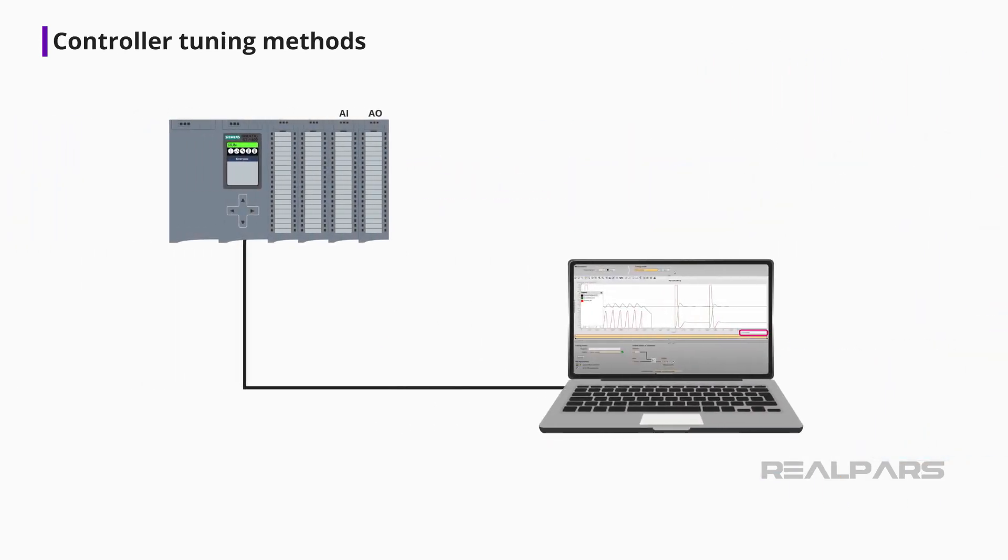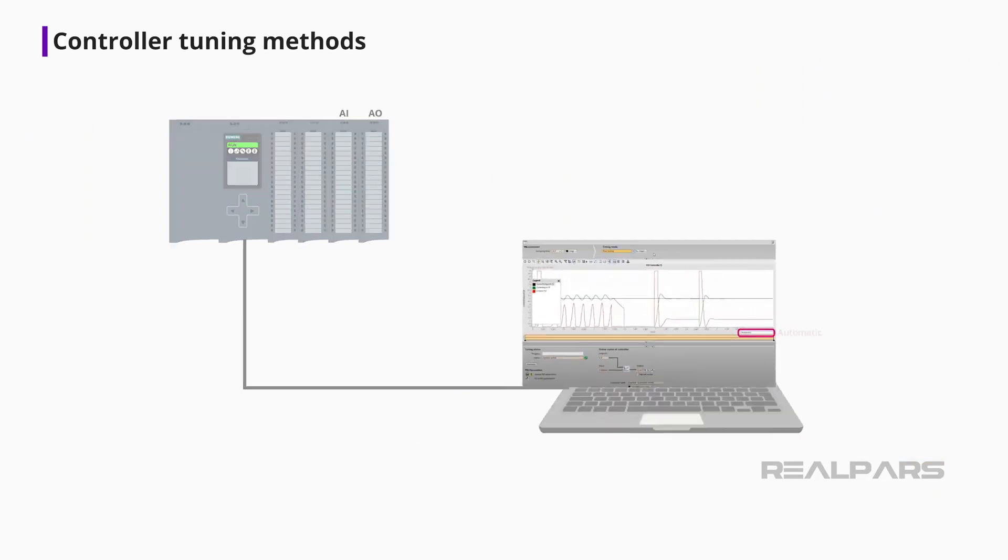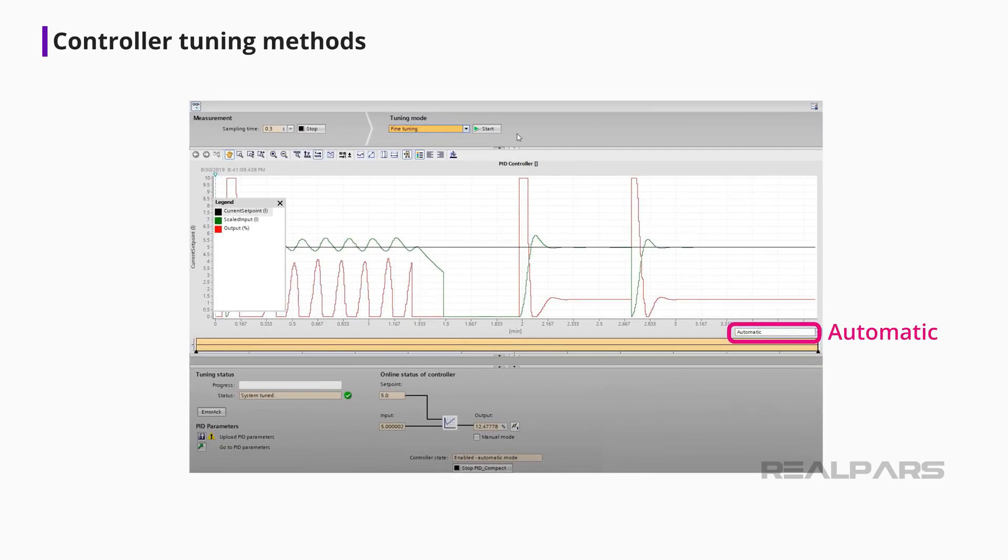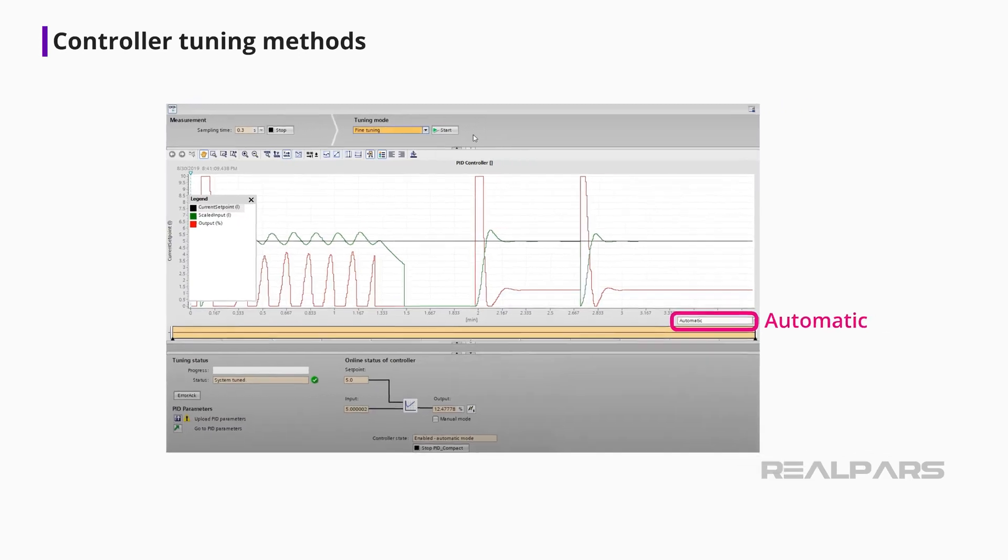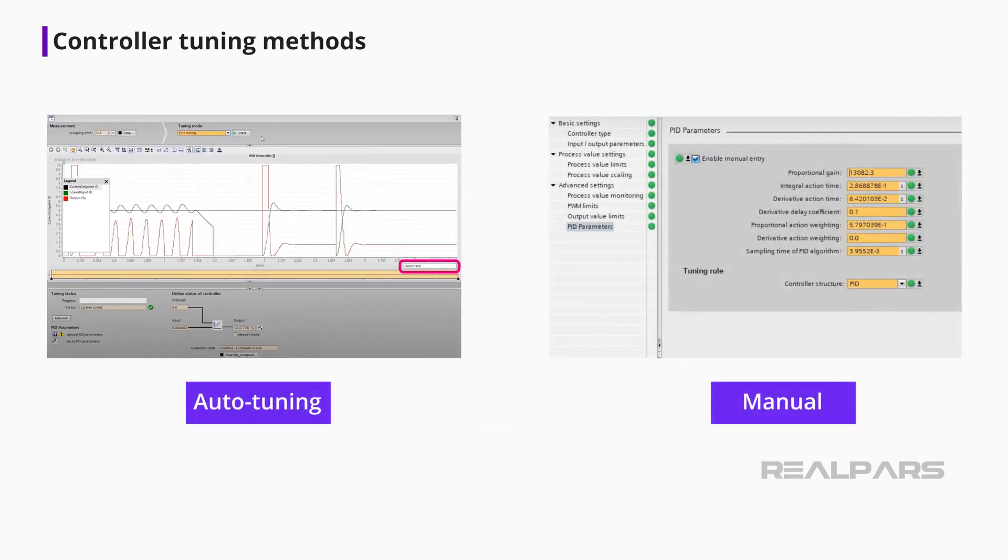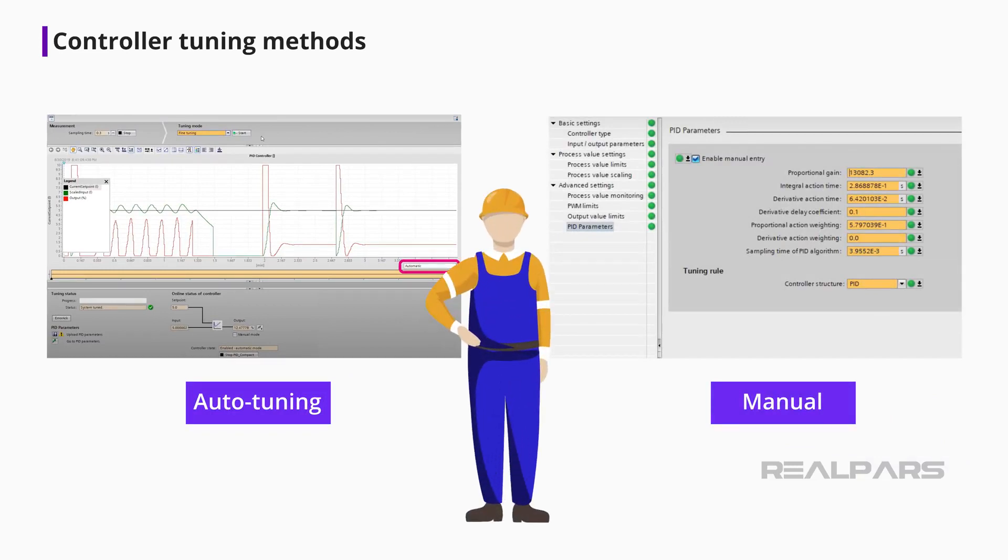Most process controllers, PLC, and DCS loop controllers sold today have auto-tuning capability. The PID controller learns how the process responds to a change in setpoint and suggested PID settings. Regardless of whether the initial PID parameters are derived from the manual or auto-tuning methods, additional tweaking is often required by seasoned automation professionals to get the response desired.